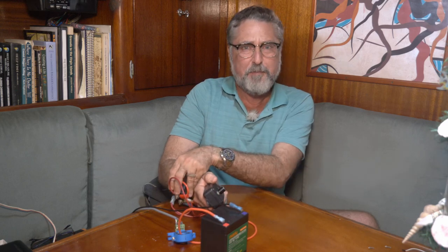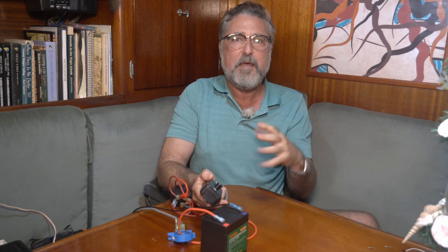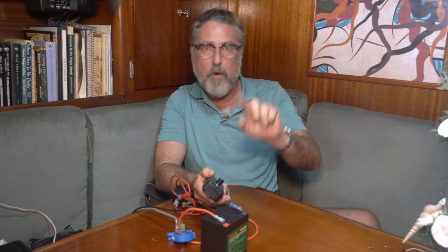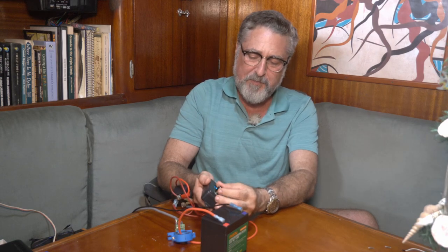Okay, contactor type, either monostable or bistable. We're using a monostable, normally open, normally closed, it's also monostable. But if you're using a bistable relay, one that has one coil that turns it on and one that turns it off, it's important that you set that. I'm using a monostable, so let me set it for monostable.